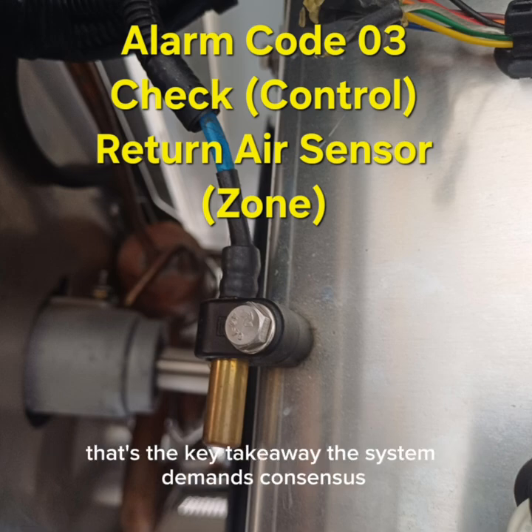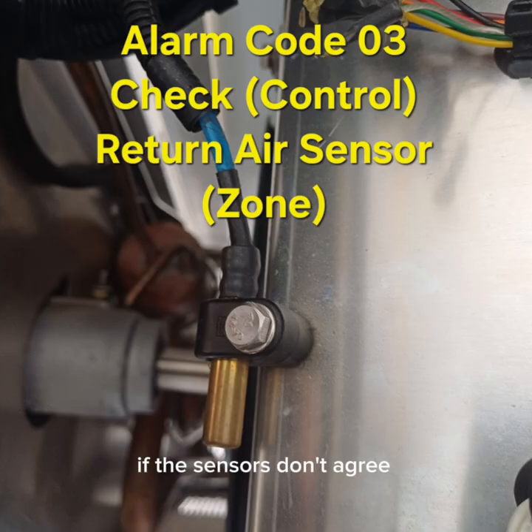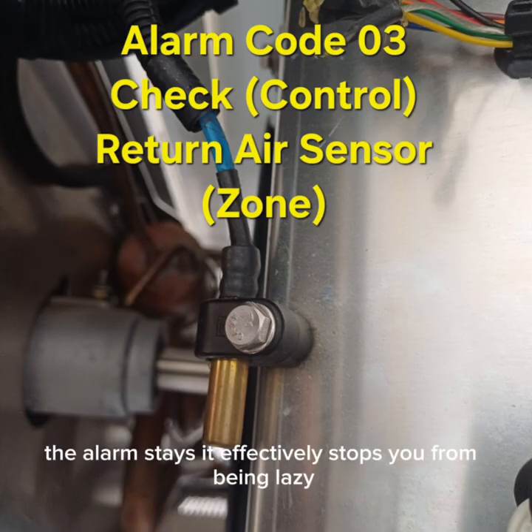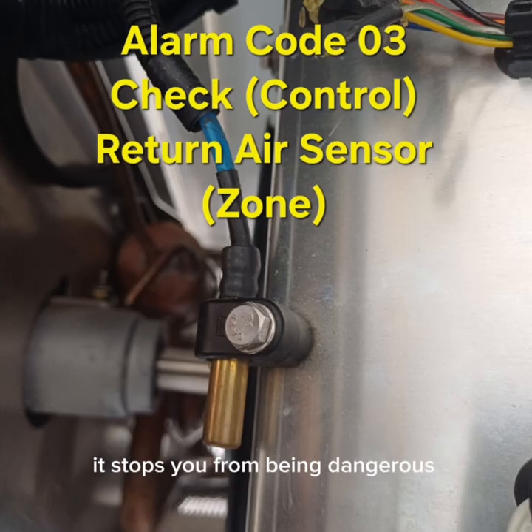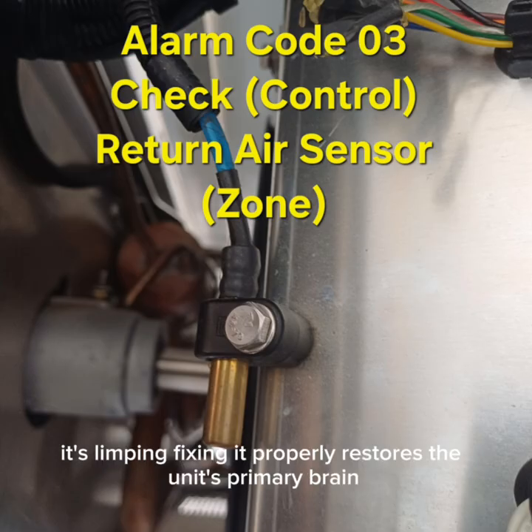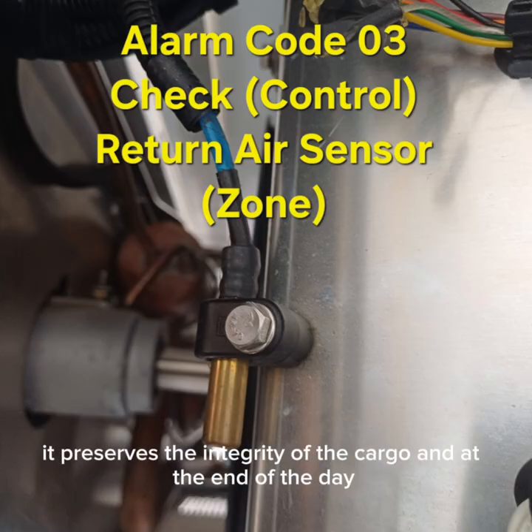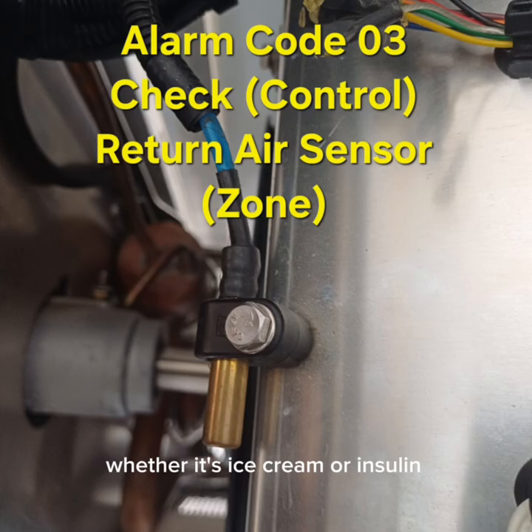That's the key takeaway. The system demands consensus. If the sensors don't agree, the alarm stays. It effectively stops you from being lazy. It stops you from being dangerous. Because remember, if alarm 03 is active, the unit is in a fallback mode. It's controlling off the discharge air, it's limping. Fixing it properly restores the unit's primary brain. It preserves the integrity of the cargo. And at the end of the day, that's the only thing that matters. Whether it's ice cream or insulin, that sensor protects it.